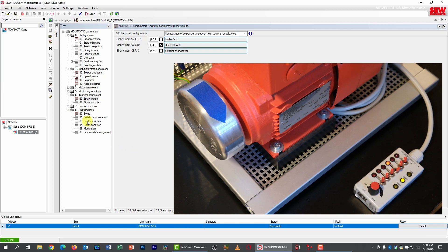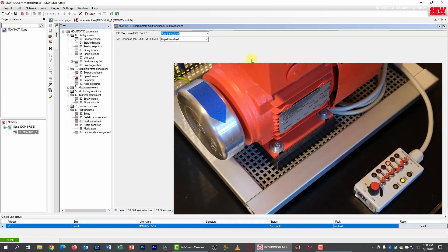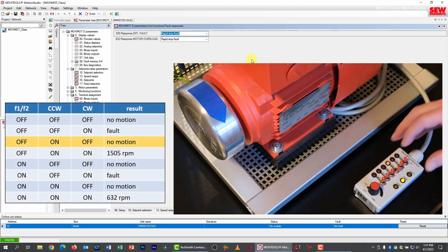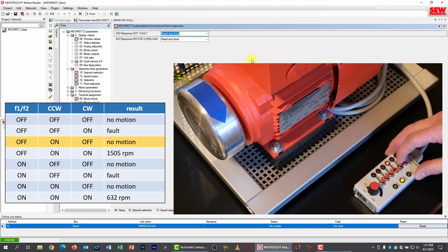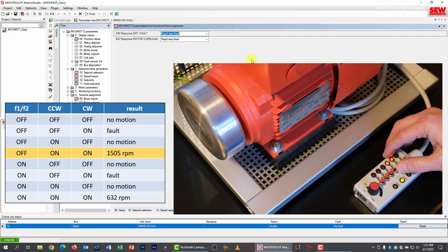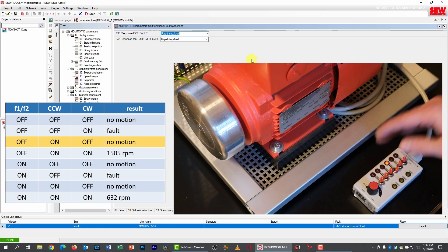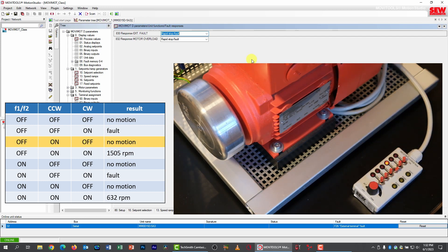I try to run the drive by turning on the clockwise input, but nothing happens. The reason is the external fault signal is an active low signal — that switch is off, meaning the signal is at ground level, signaling a fault. The Movimot is now faulted; the indicator on top is red and the status window shows fault 26, external terminal fault. I need to turn that switch on to signal nothing is wrong, then clear the fault. As soon as I do, the drive starts running.